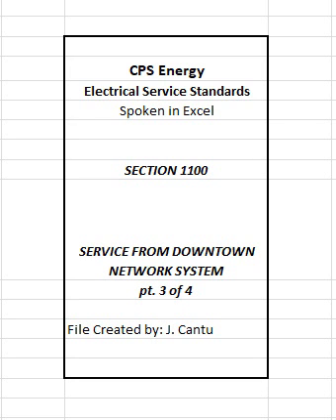Such raceways shall extend not more than 4 feet inside the building. For greater distances, customer must obtain approval from CPS Energy and install raceways in a manner that will render them as being outside of the building. Refer to definition of conductors considered outside of building. Service lateral raceways installed ahead of CPS Energy metering equipment shall be rigid metal conduit (RMC), intermediate metal conduit (IMC), or bus duct. All raceways shall be continuous except for couplings.